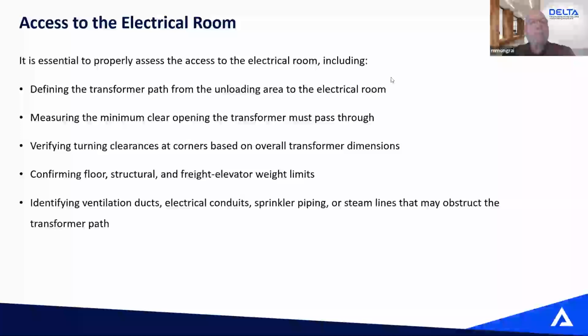One other thing that is also very important is to assess the access to the electrical room. Again, back in the days, or when you build a new building, it's easy. You drop the transformer in place and you build the building around it. But when you have to replace that transformer, you need to make sure that from where we're going to deliver the transformer, so from the unloading area, it can be a loading dock, it can be in the street.